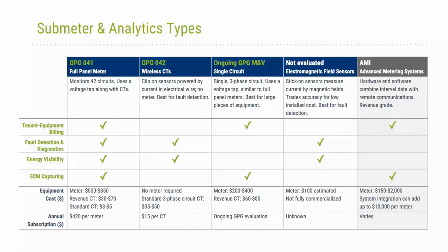The same thing for the electromagnetic field sensors. They're great for fault detection and diagnostics and energy visibility. However, the error is unbounded because of the interference between adjacent breakers. Whether you have a big load on one and a small one on the other, there's no guarantee on the error.